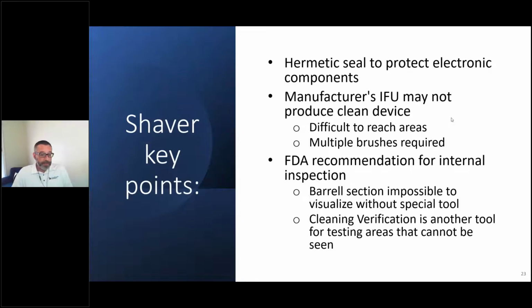I do want to point out, though, that cleaning verification is another tool you can use, so it doesn't always have to be visual. But the FDA did come out and say you've got to do something. We've asked the manufacturers to reevaluate their IFUs, but from a user perspective, from a person on the ground trying to clean this, you've got to do something to ensure these are clean.